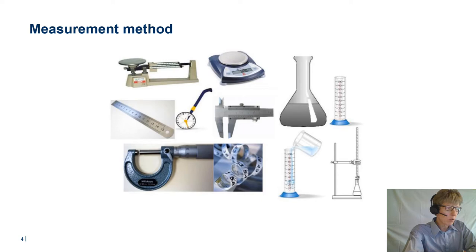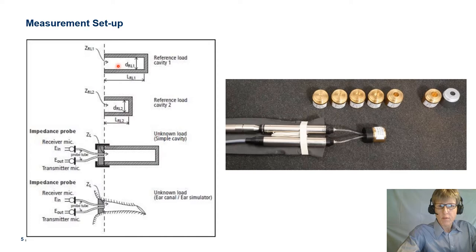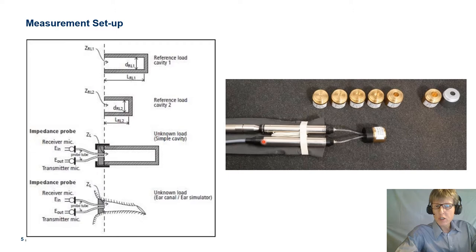As illustrated to the left, we have the known reference load cavity 1 and cavity 2. The impedance probe is in turn connected to reference load cavity 1, 2, and the unknown load — shown as a simple cavity and below as an ear canal or ear simulator. To the right, we see the impedance probe device in more detail, with the transmitter probe microphone and the receiver probe microphone connected using two thin tubes to the reference load via an airtight interface. We have a total of seven different reference load cavities, and to the right we see a more complex load, the IEC 711 coupler, which uses the same interface.